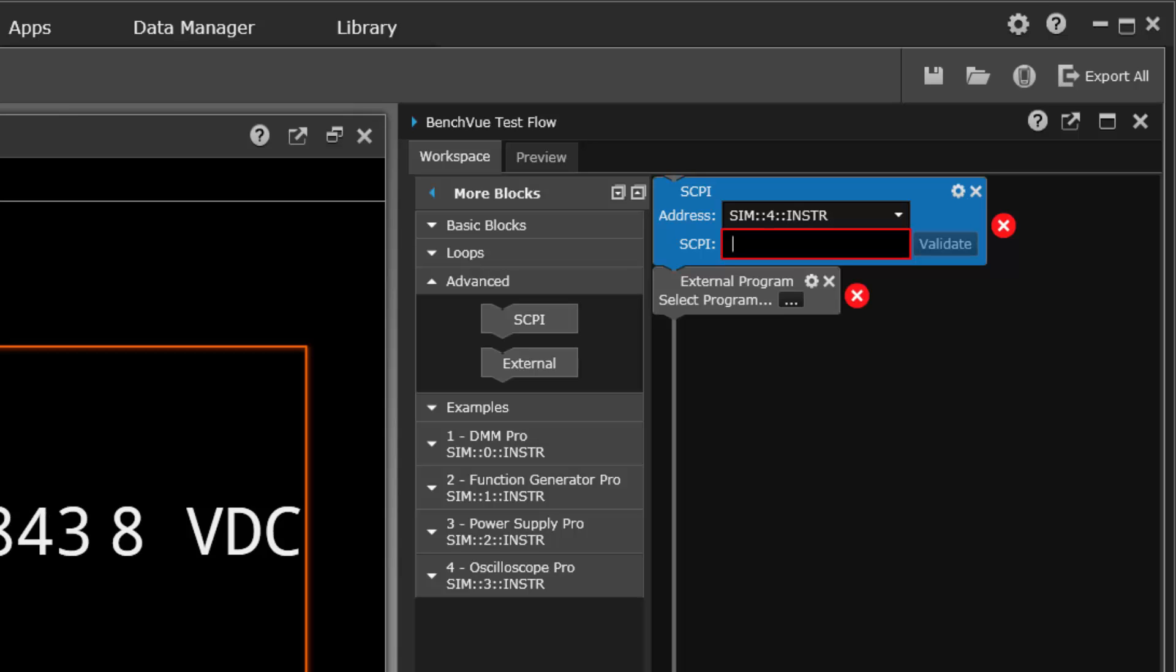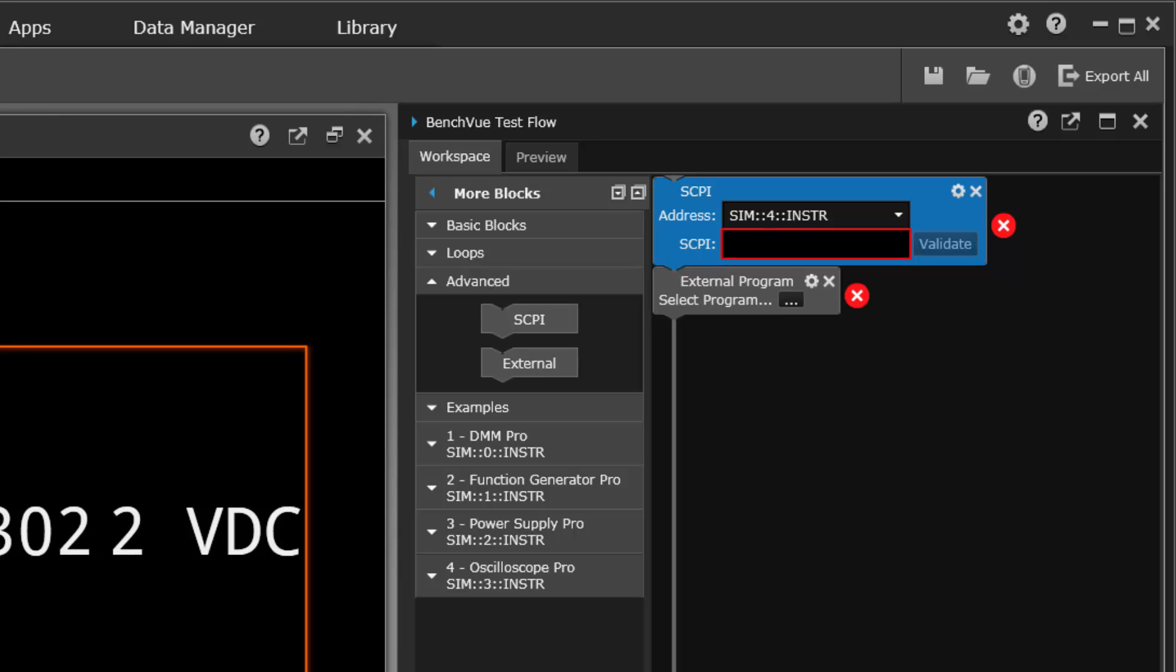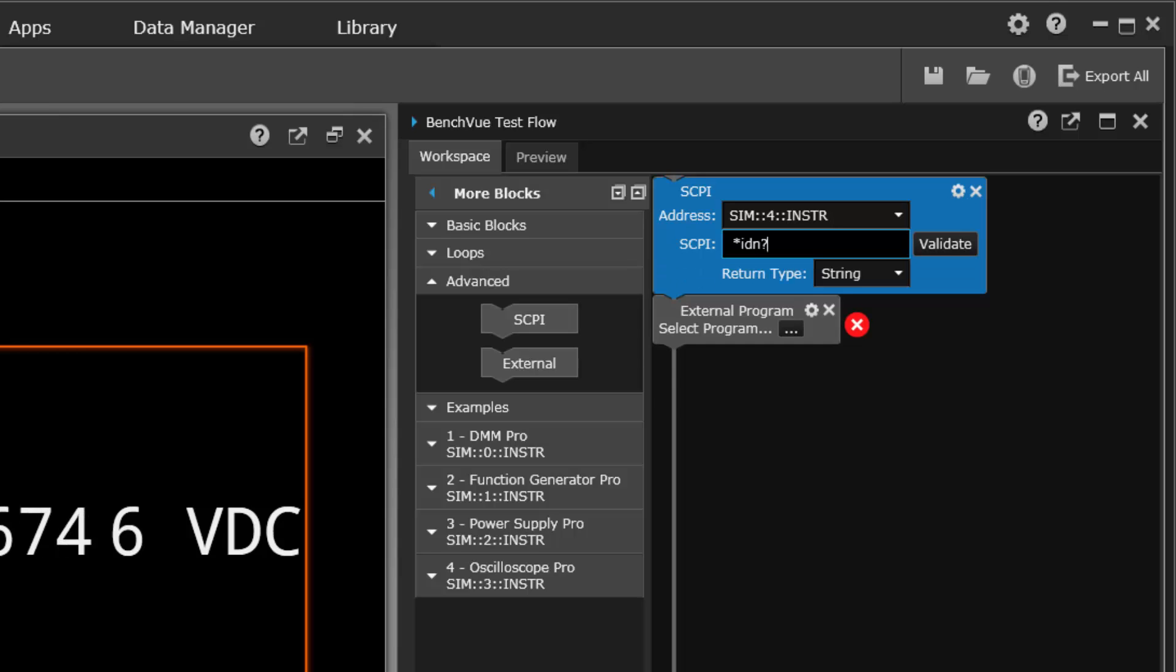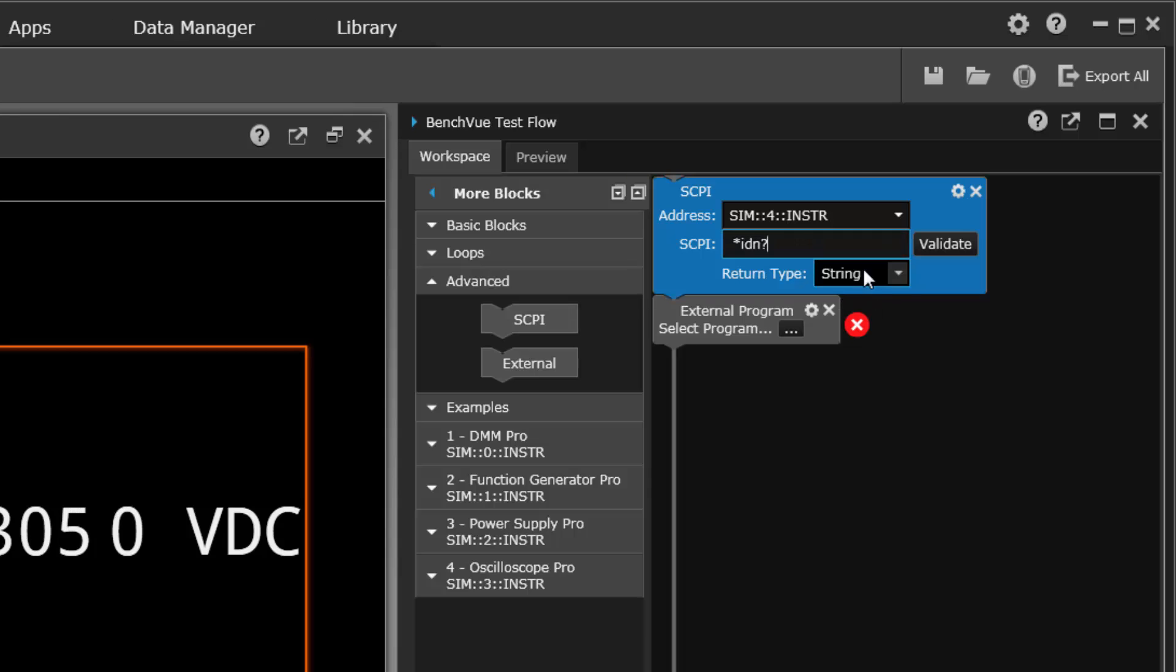Even when you use drivers, you're basically inside the driver using SCPI commands. So a typical one might be star TST for a test routine or IDN query. When you put a question mark on there, it knows that it's a return value and it will return the value and then show you the results. These all are logged.